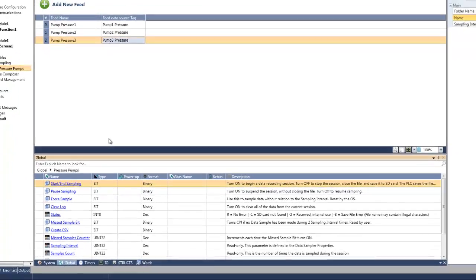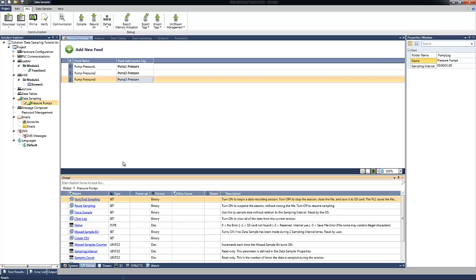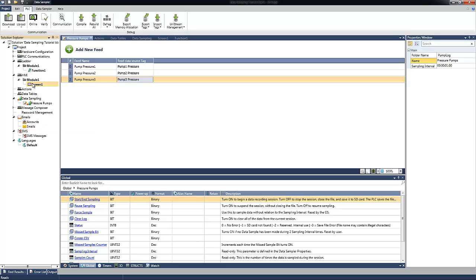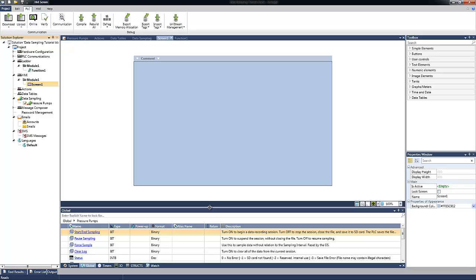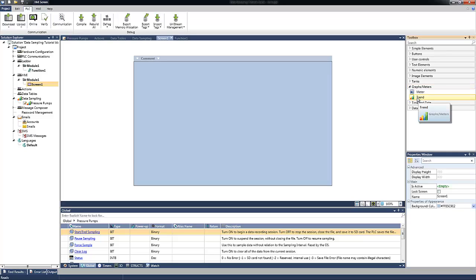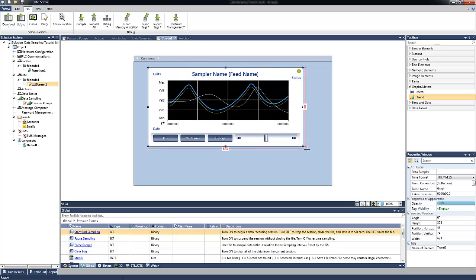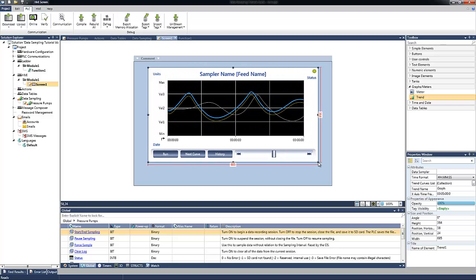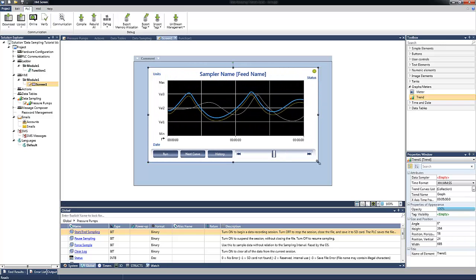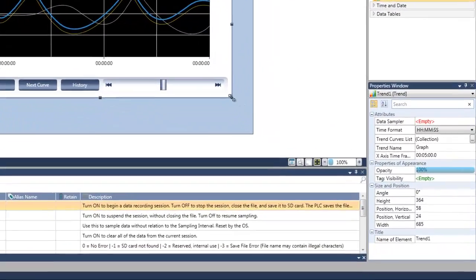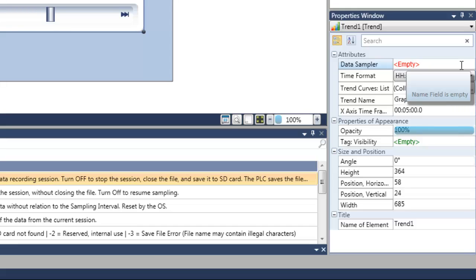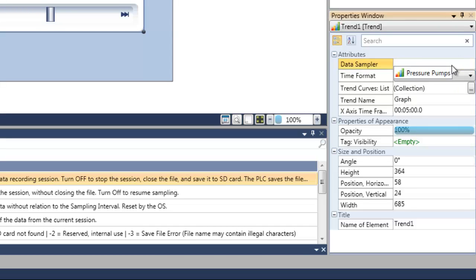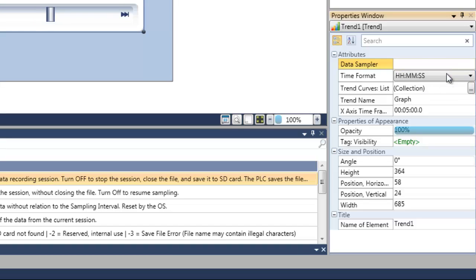Now, let's make use of the data sampling. For example, if we want to see the data sampling as a graph on the HMI, we can use the trend variable. I will open the HMI window and add from the graph and meters, I will add the trend variable. Using the cursor, I can drag and draw the trend variable on the screen. In the properties window of the trend, first of all, we need to configure the source of our data sampling. Let's click on the data sampler and select our Pressure Pumps, which is the data sampling.